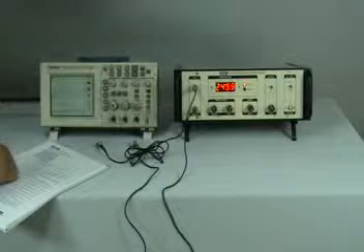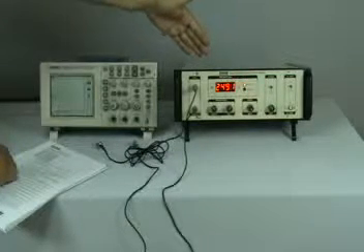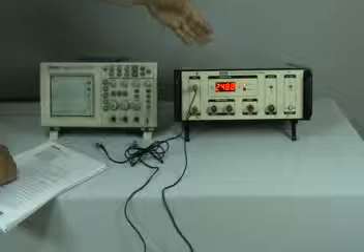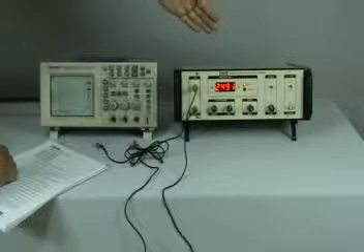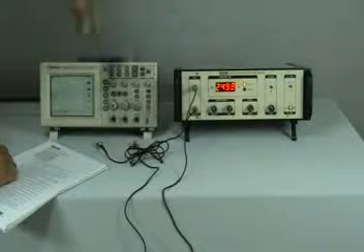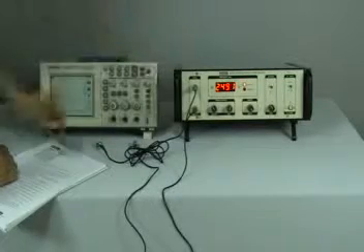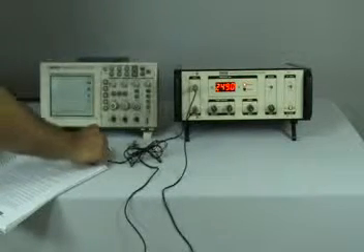We need to switch on the instrument from the back panel and the LED display will light up, indicating the frequency in megahertz. This is the center frequency for the RF input to be connected at the SMA connector. The instrument is to be connected to the CRO using the BNC cables provided.